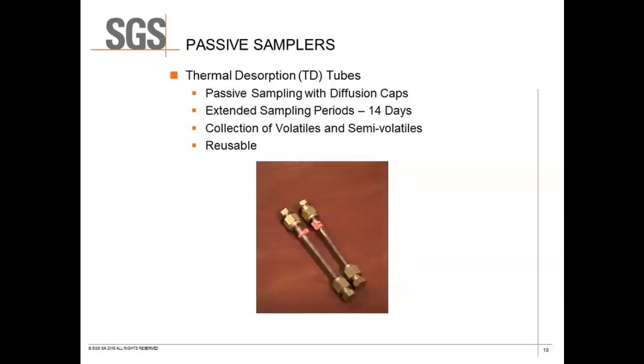TD tubes can collect not only volatiles but also many semi-volatiles, making them very versatile media. Another advantage is that they're reusable: once analyzed, the tubes are heated, cleaned, and conditioned — contaminants and moisture are removed — and then they can be reused. This is a real cost-effective feature.